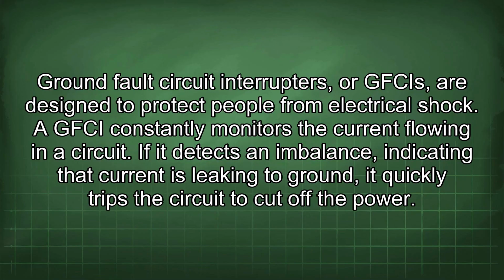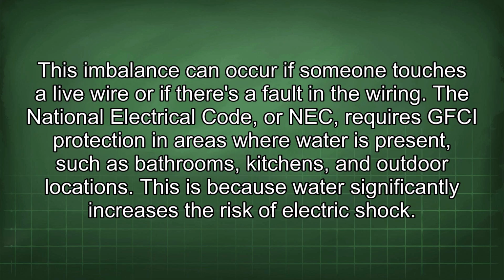Ground fault circuit interrupters, or GFCIs, are designed to protect people from electrical shock. A GFCI constantly monitors the current flowing in a circuit. If it detects an imbalance, indicating that current is leaking to ground, it quickly trips the circuit to cut off the power. This imbalance can occur if someone touches a live wire or if there's a fault in the wiring.